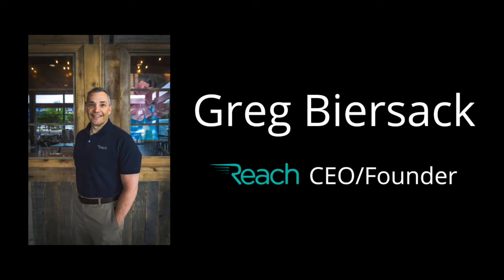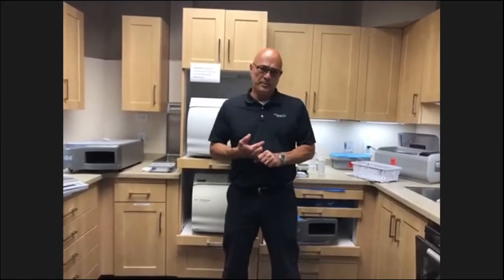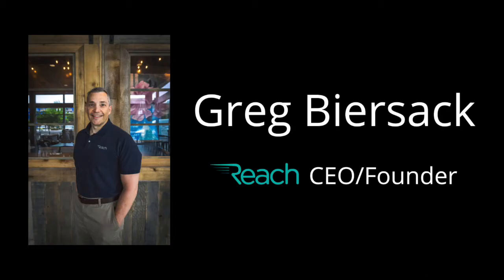Okay, great. Thank you so much. Next question: how about documentation? What kind of documentation should be done regarding those tests? You should definitely keep a log of your findings, whether you're doing it in-house with the spore tests, or if you're doing a third-party spore test, then they would send you that documentation. Definitely keep any kind of documentation like that for, I believe, a minimum of 5 years.